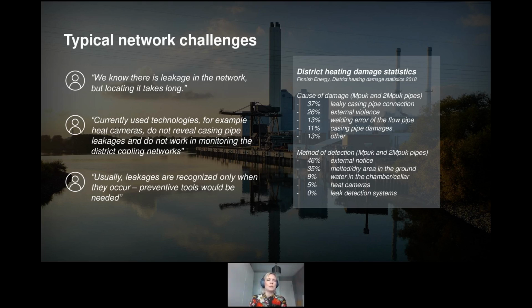Typical challenges when it comes to leak detection that we have been hearing from our customers are, first of all, they know there is a leakage, but locating that leakage takes too long. Secondly, we keep hearing that heat cameras, which are quite popularly used, are really good, but they do not reveal any problems in the casing pipe, so water getting inside the insulation, not the district heating leakage actually coming out from the pipe. And this kind of heat camera also cannot reveal district cooling leakages that easily.